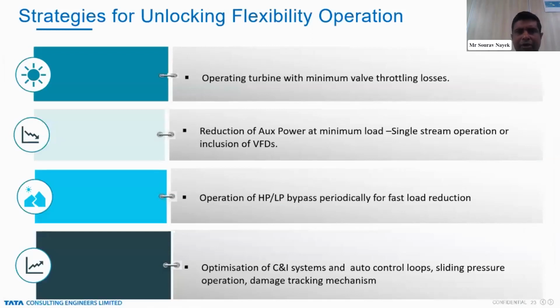Now, what are the strategies for heat rate improvement during flexible operation? We should operate the turbine with minimum throttling losses. We should reduce the auxiliary power consumption at minimum load, either by single stream operation or by including VFD. The payback has to be checked for inclusion of the VFD, so that we get the benefit in operating cost. The HP and LP bypass should be periodically operated so that faster load rejection happens. The C&I system and the control loops also have to be optimized. Sliding pressure operation and a damage tracking mechanism have to be established in the plant.